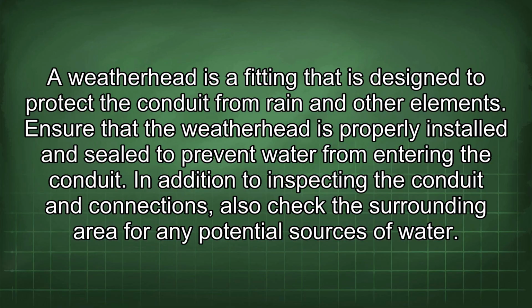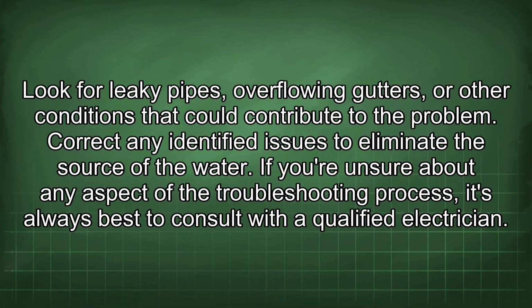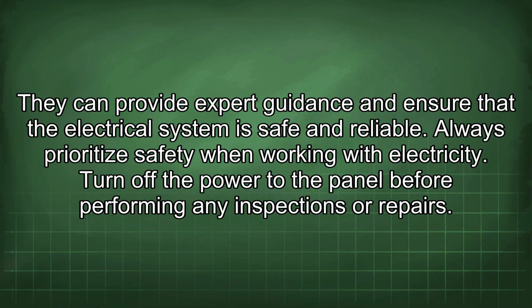In addition to inspecting the conduit and connections, also check the surrounding area for any potential sources of water. Look for leaky pipes, overflowing gutters, or other conditions that could contribute to the problem. Correct any identified issues to eliminate the source of the water. If you're unsure about any aspect of the troubleshooting process, it's always best to consult with a qualified electrician. They can provide expert guidance and ensure that the electrical system is safe and reliable.